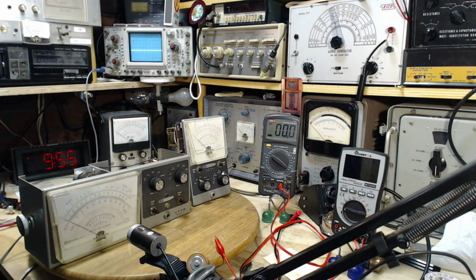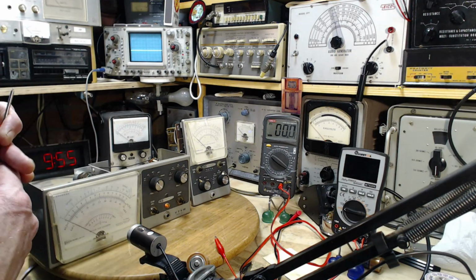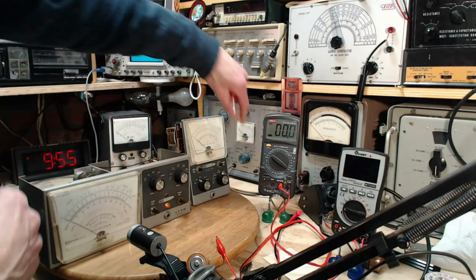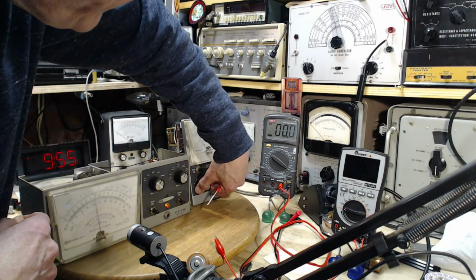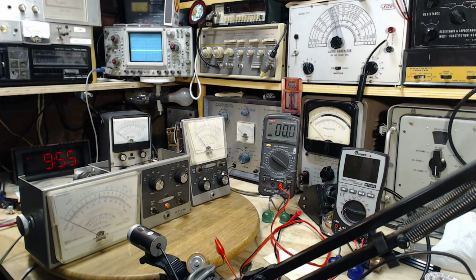Next step, after doing the mechanical alignment: turn the instrument on, set the function switch to DC plus, check operation of zero adjust control. Turn the units on, set them to DC plus.